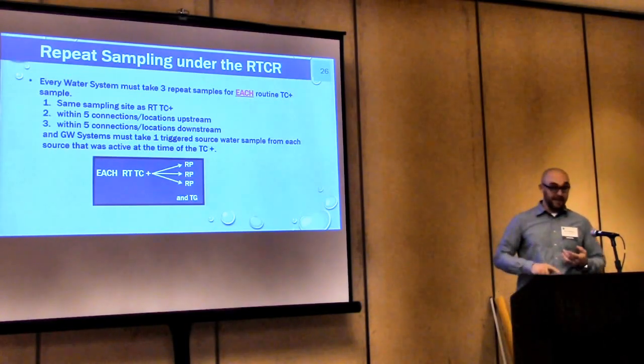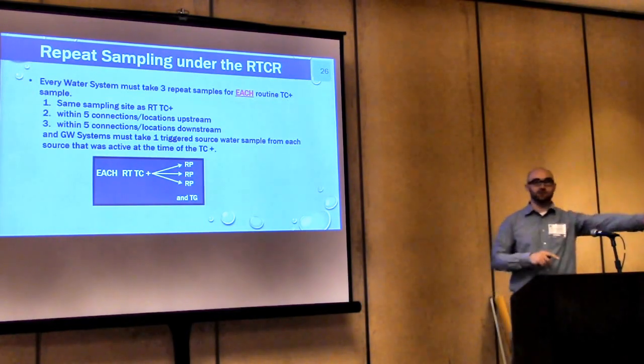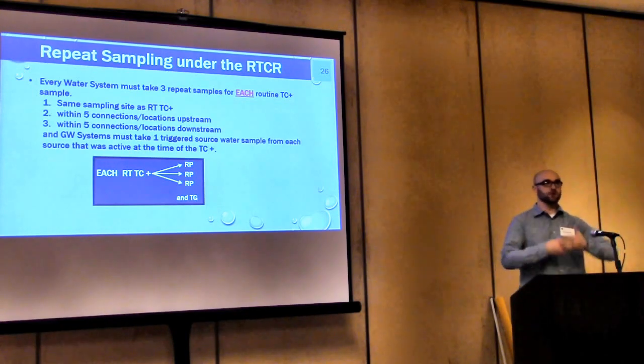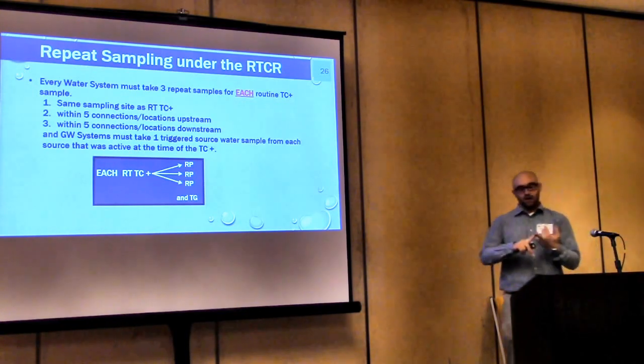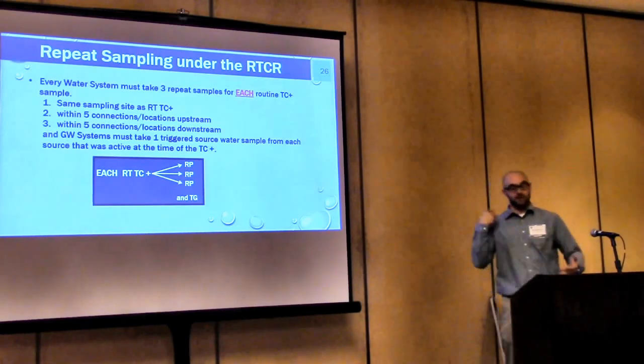Those repeats are taken at the same location as the positive, a location within 5 connections downstream, further from the source or further from storage or down the flow of water, and within 5 connections upstream, so closer to the source, upstream, up the flow of water.